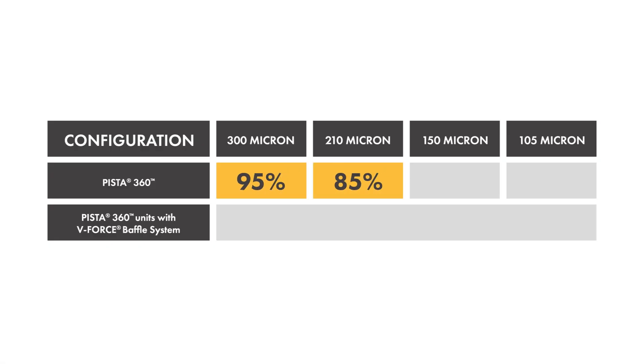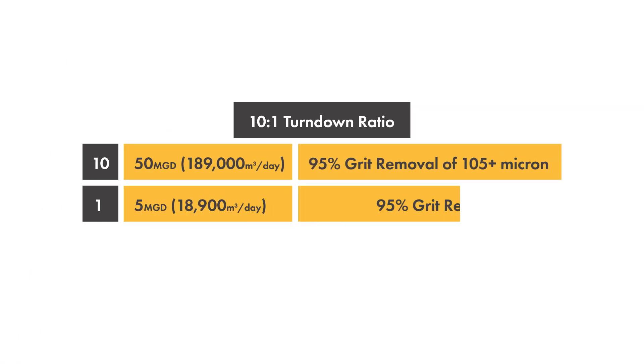The V-Force Baffle creates a forced vortex that allows 95% grit capture of 105 micron particles at all flows with its 10 to 1 turndown ratio. For example, a 10 to 1 turndown ratio on a 50 MGD unit will maintain the 95% removal rate of 105 micron and larger for flows from 5 MGD to 50 MGD.